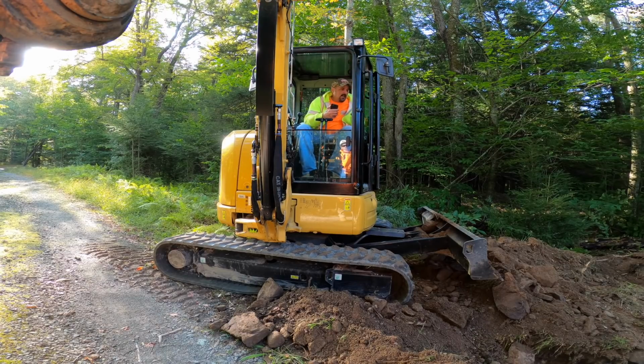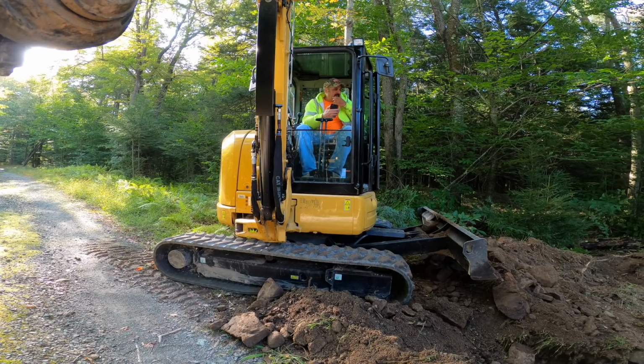Sure, yeah. And their conduit that we're following, we haven't been able to get our full depth the last 50 feet because there's more conduits underneath, and so we're following the one on top, but getting our conduit to the side of it, and the top of our conduit is the bottom of their conduit. You know what I mean? So we're a good 4 inches below.